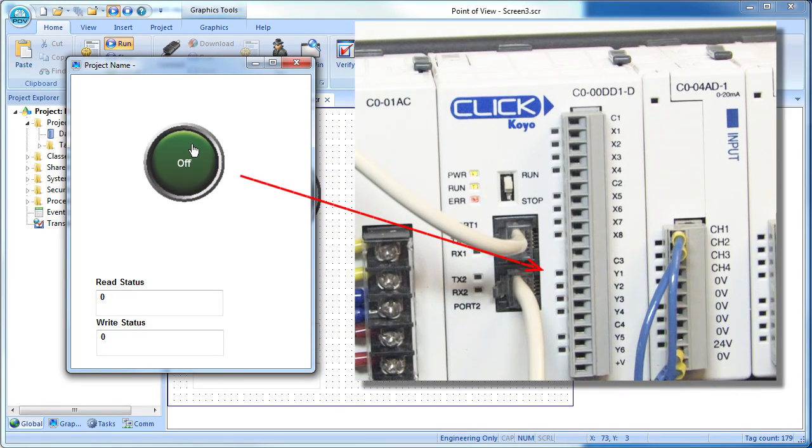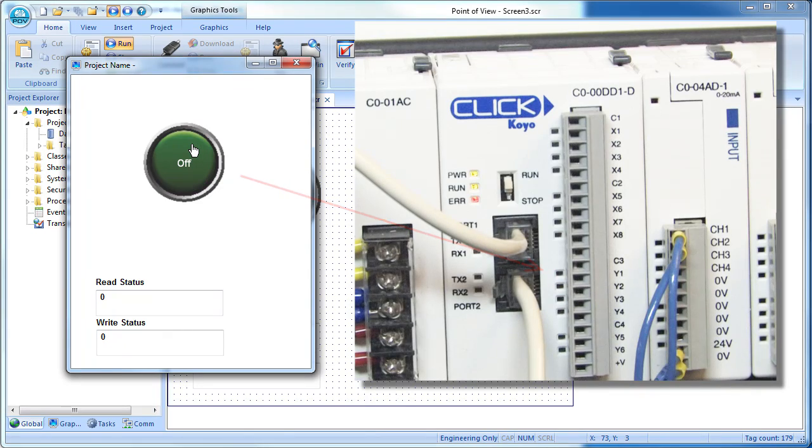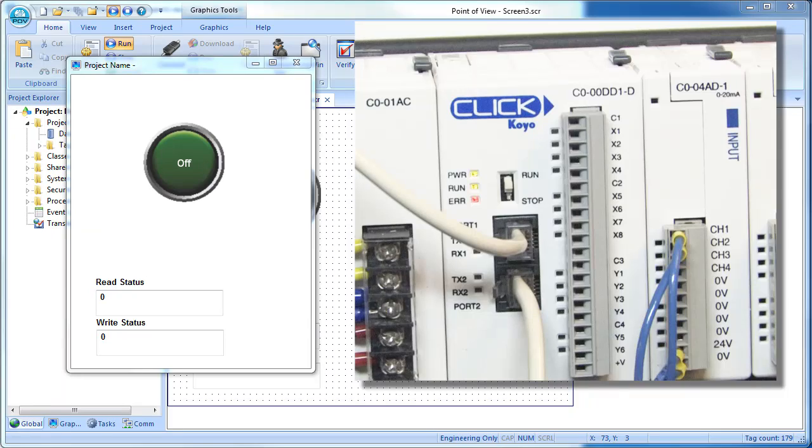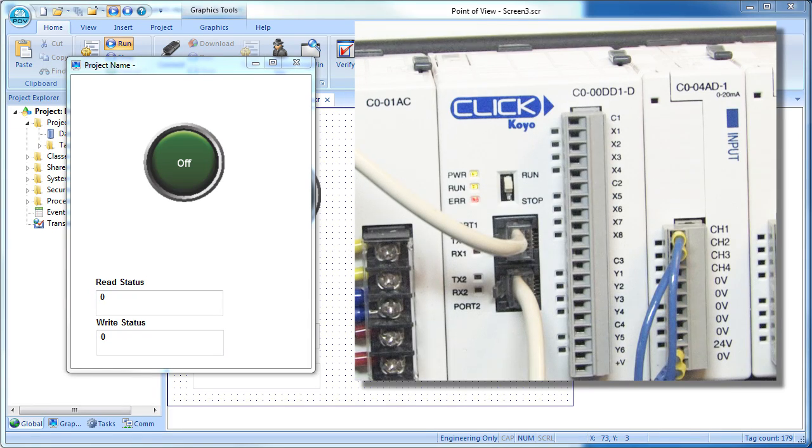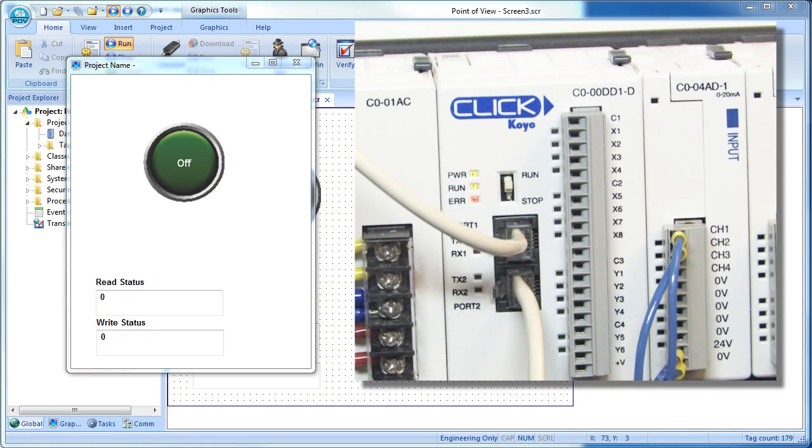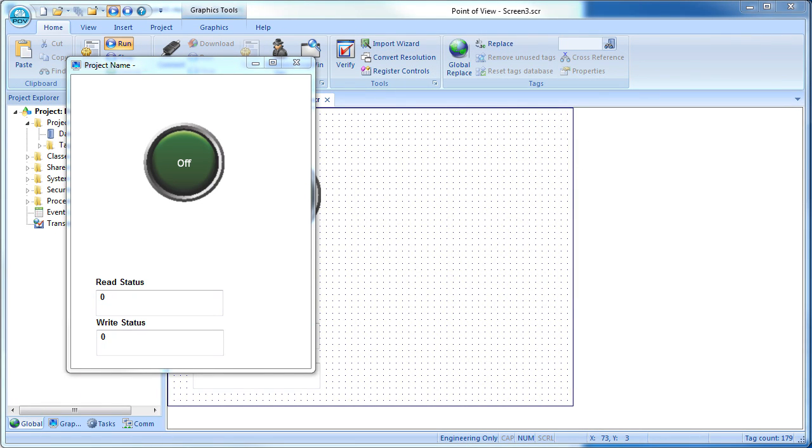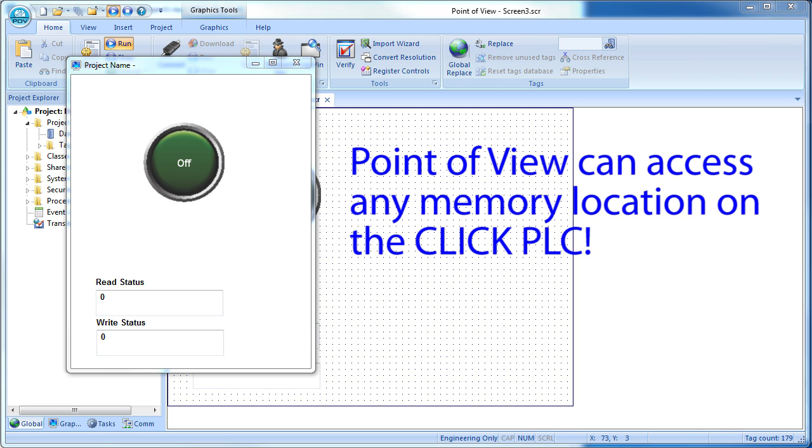By the way, I should mention, best practices dictate that you never do this in a real project. You would never want to control a PLC output directly from Point of View. You would normally control a tag on the PLC that controls the output. That keeps the local PLC ladder code in charge and is a much safer way to run your system. We just did it here because it demonstrates that Point of View has access to any Modbus addressable register on the PLC.